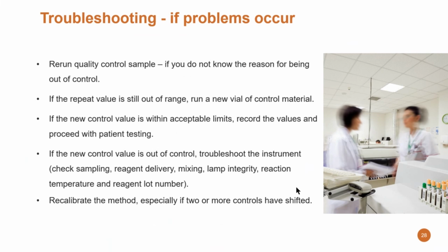The last step I would recommend is to do a recalibration of the method. Because if you calibrate and there is an error on the instrument, on the reagent, or the combination of both, you may calibrate this error away, and it may come back later in the month or the week. So be careful and have a good reason when you do calibration or recalibration of your method.